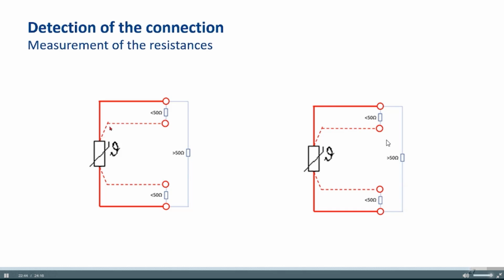Let's look. If you measure between the 2 wires which are on the same side, you would measure only a very small value, maybe 2, 3 ohms, something like this. Here I said if you measure something below 50 ohms, then you know this is one side of this RTD temperature probe. So the corresponding wires always have a value below 50 ohms. It doesn't matter if you have a PT100 or PT1000. If you measure between the wires of the other side, then you can always expect values higher than 50 ohms. It doesn't matter if you have a PT100 or PT1000.